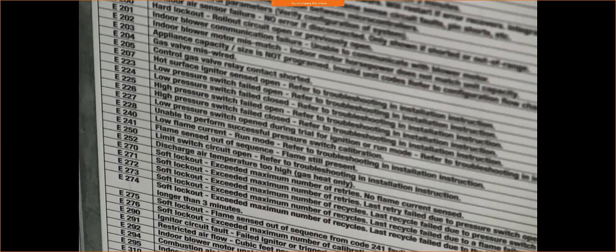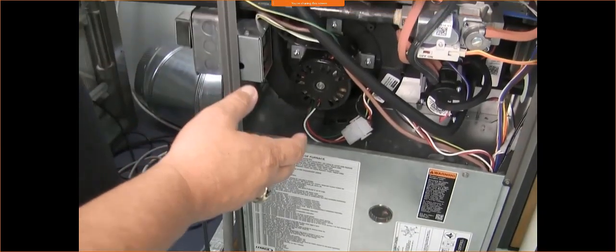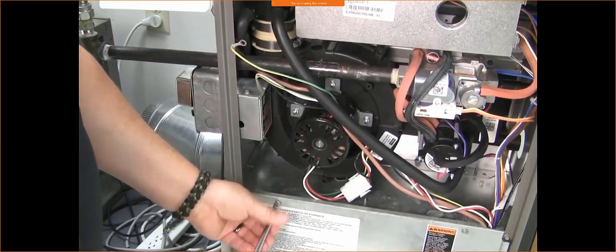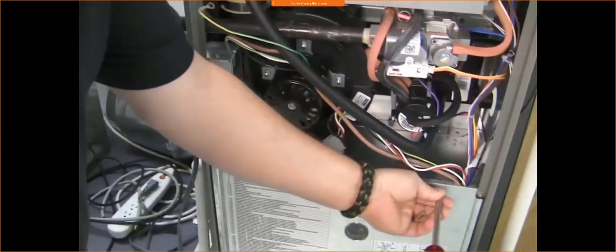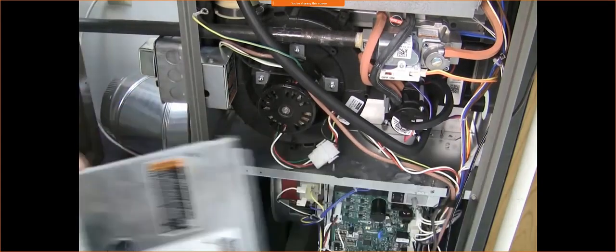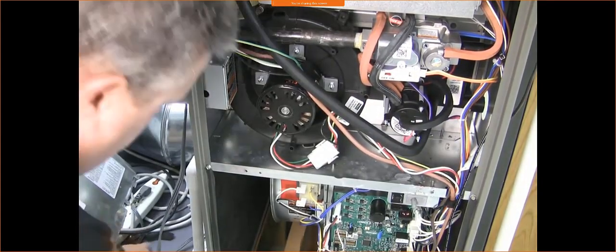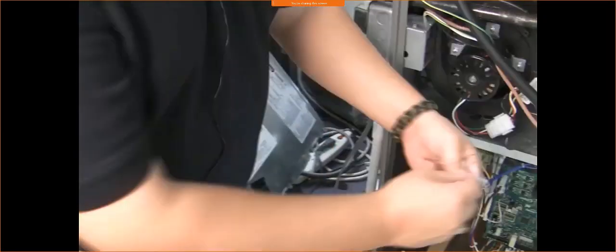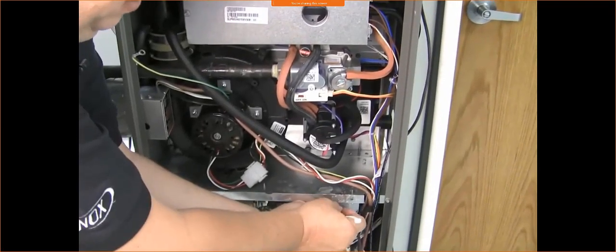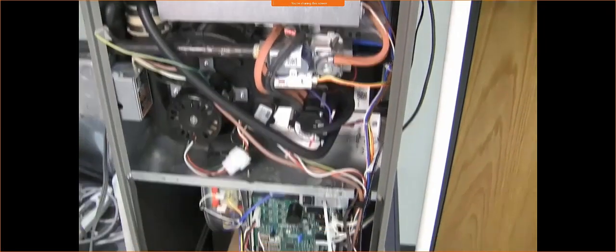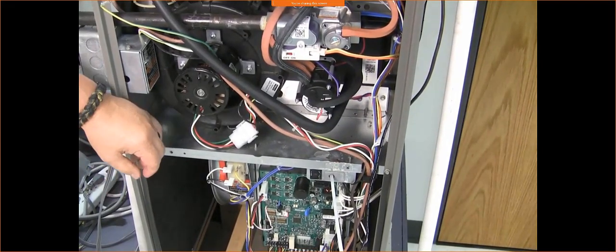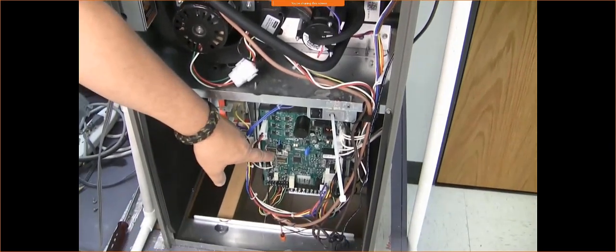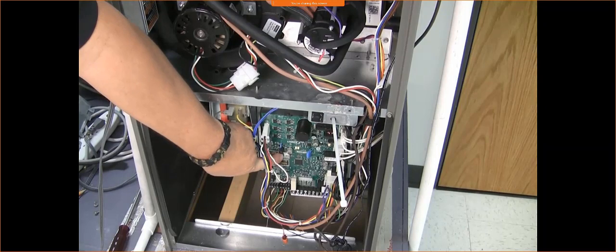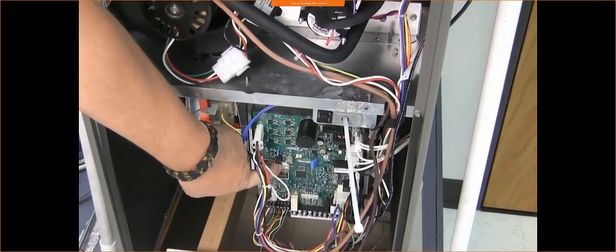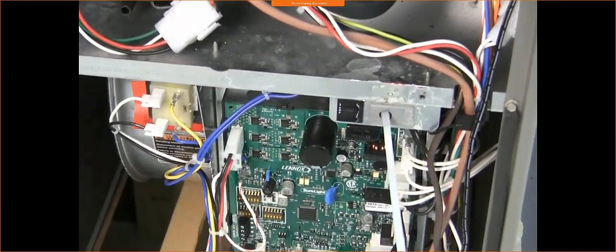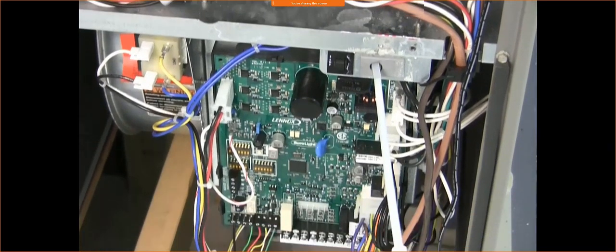Now, if I forget to check the fault code before I disconnect power, I very simply have to remove the door, then most people use tape. I prefer to use a wire tie to bypass the safety switch on the door. Okay, reapply power, and when you get the small pulse, you simply push the white button and hold it until you get an E. Once you get the E, you release, and then it will start running through the fault codes again.